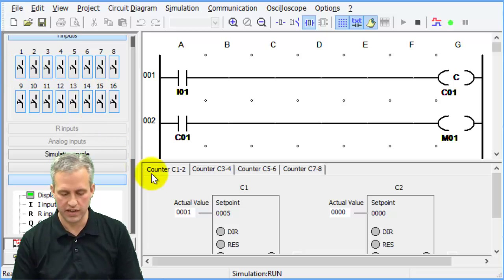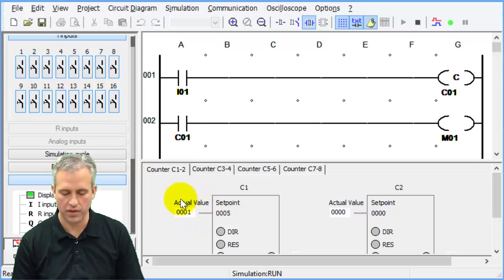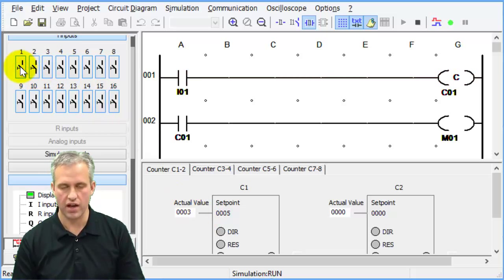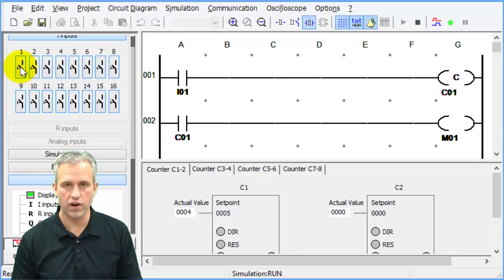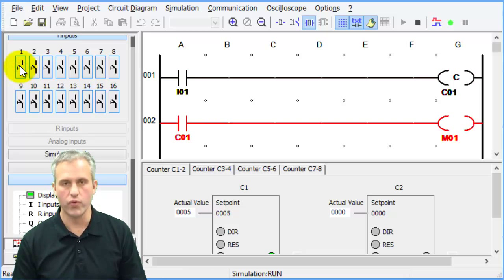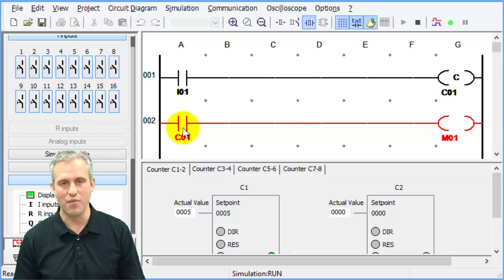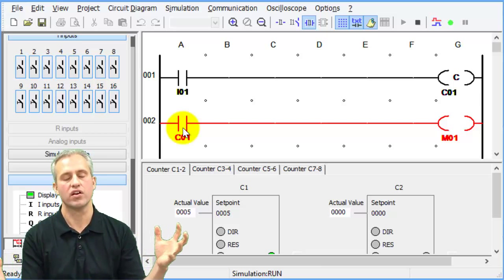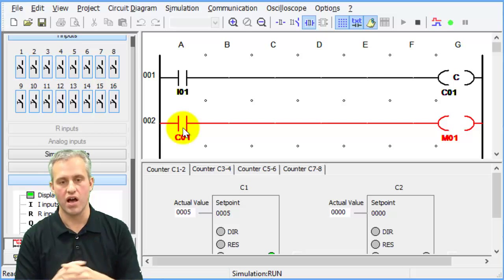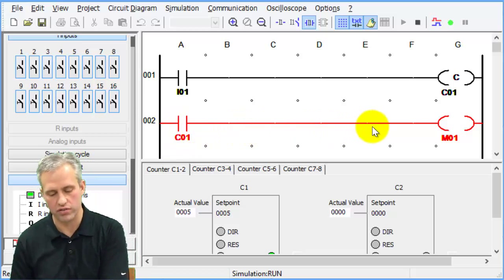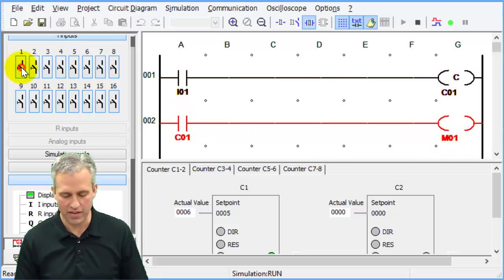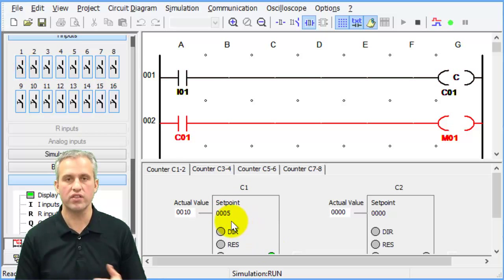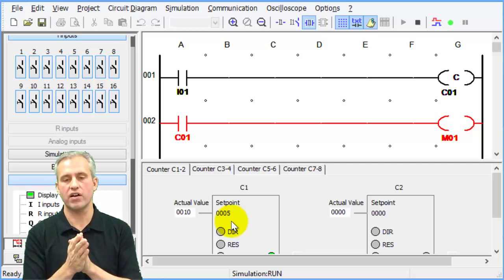I'm going to hit play and if I hit I1, you can see that not a lot happens on the screen except for the value has incremented to one here. If I hit it a second time and then a third time, going nice and slow because Microsoft likes nice and slow clicks, four, not too exciting. Here it comes, wait for it, woohoo, five. So when you go to five, it makes that counter relay go into the made state. When it's in the made state, it's going to allow current to flow through its rung and turn on marker one. You can keep clicking and the actual value will just get higher and higher and higher. So really the set point is, is my count value equal to this number or greater, that's really what it's asking.